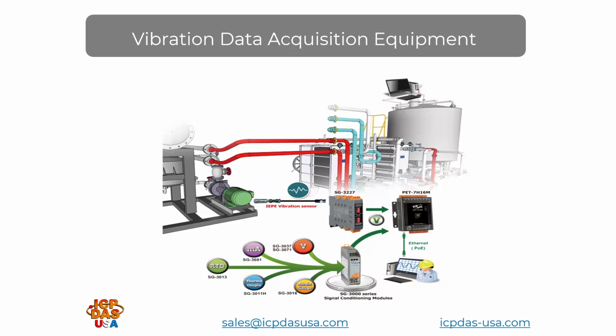7H16M, which is a high-speed data acquisition module. It includes 8 high-speed 16-bit single-ended analog inputs, 200 kilohertz sample and hold for 8 channels. It has 4-channel digital inputs and 4-channel digital outputs, and provides a programmable input range on all analog channels. You can choose plus or minus 5 volts and plus or minus 10 volts. And digital outputs can be configured with short circuit protection and overload protection. The counter values of the 4-channel low-speed digital input counters and the 1-channel high-speed counter are latched by ADC sampling times synchronously.